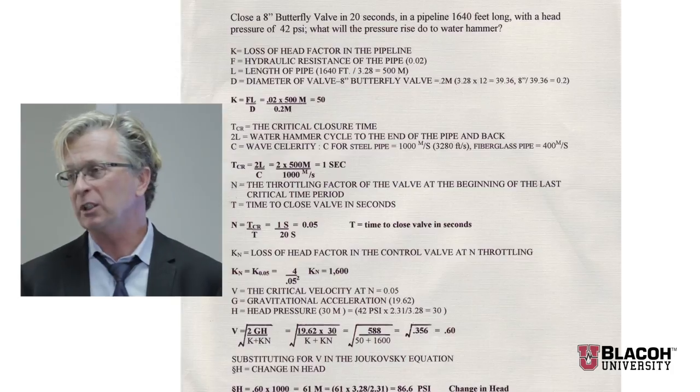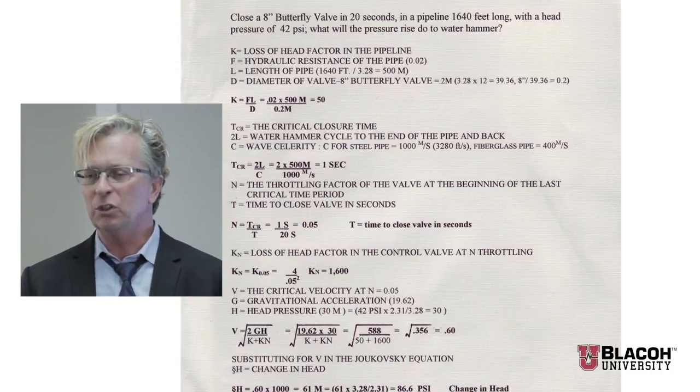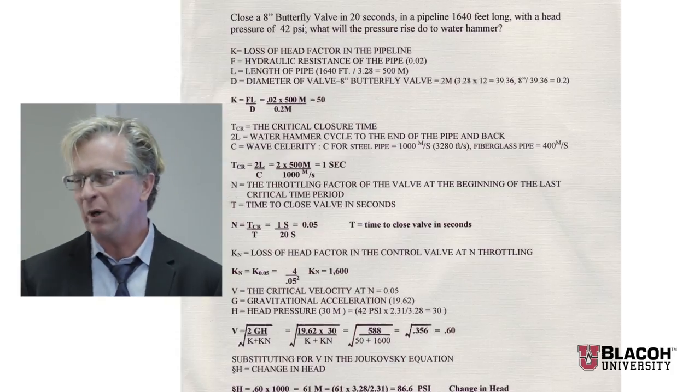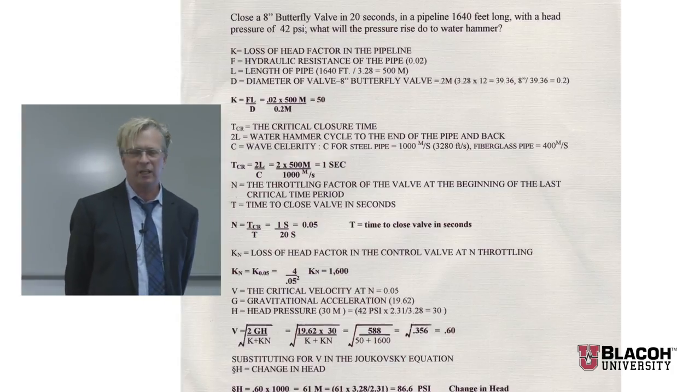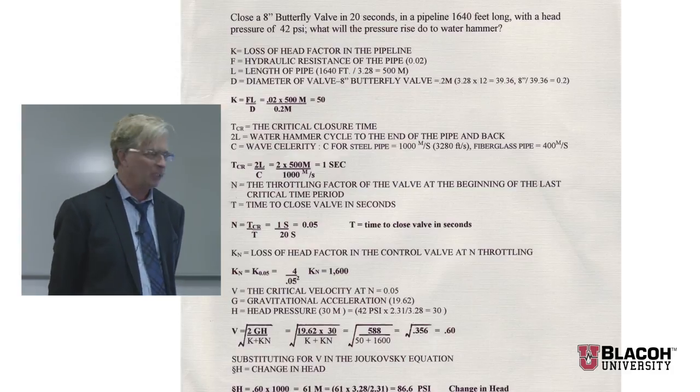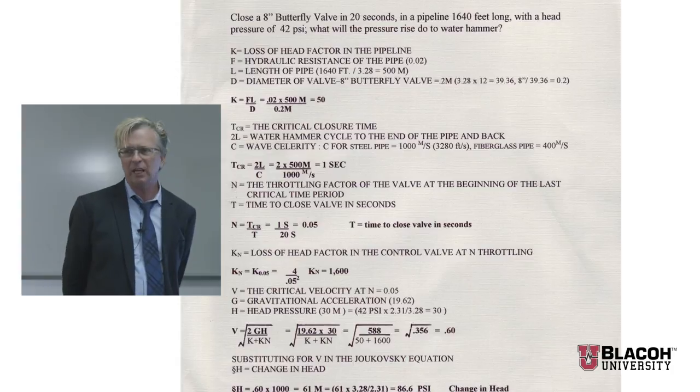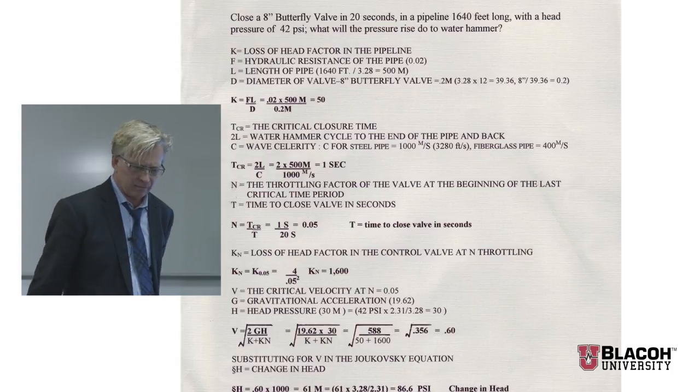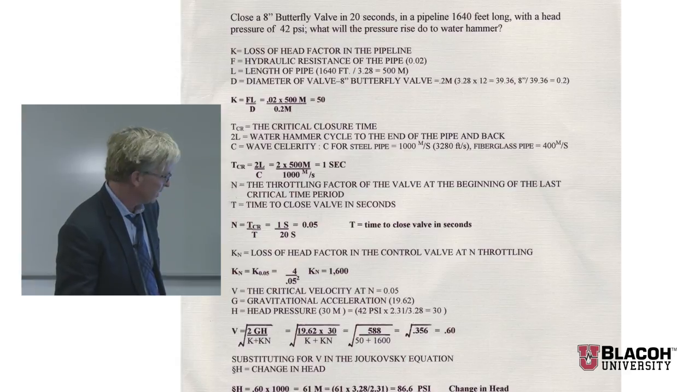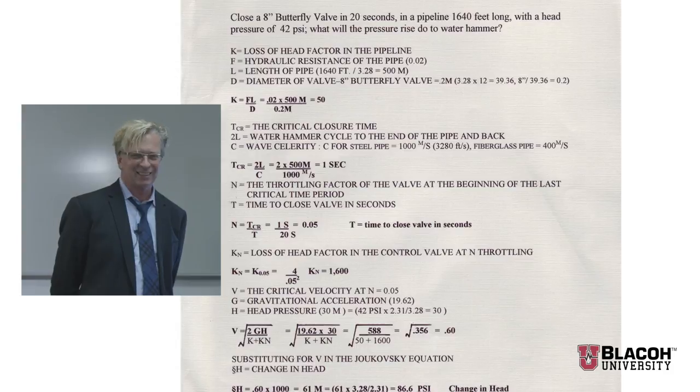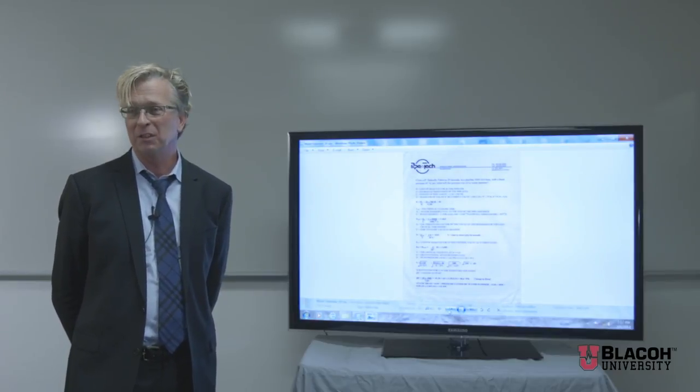The wave goes out and comes back in literally one second. If you had a pressure transmitter recording pressure waves once every second, you may or may not record that pressure wave occurring. In our system we're looking at a water system running at 42 PSI, relatively low pressure. We're closing the valve first in 20 seconds.